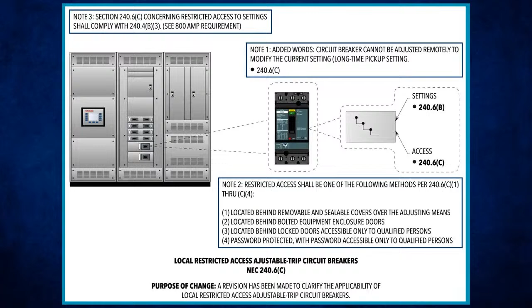The first method is located behind a removable or sealable cover over the adjusting means. The second is located behind bolted equipment enclosure doors. The other is located behind locked doors where it's only accessible to qualified personnel. And the last one is where it's password protected, and those passwords are only accessible to, once again, qualified personnel. So those are the changes they made here to deal with local restricted access adjustable trip circuit breakers.